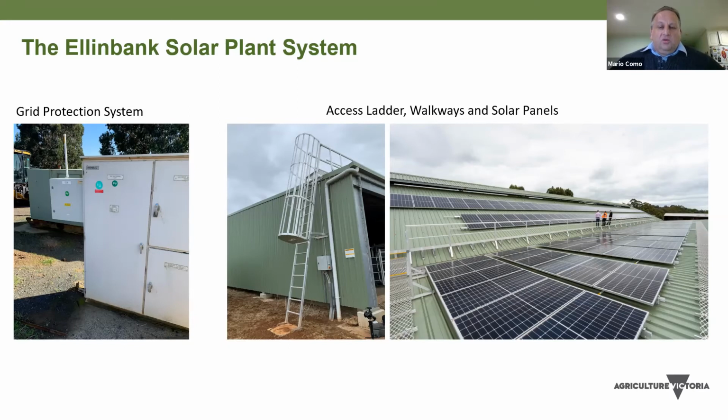We selected not to put the solar panels on a pitch on the other roof, mainly because it would have occupied a much greater area, because we have to allow for shading. Also, within our budget, the cost of actually creating the stands that configure the pitch will also add to the cost. So, with a 12% efficiency reduction, we thought that was a way to go. I think Geoff mentioned 15%, and we're currently monitoring the efficiency of the system. It has peaked at 102 kilowatts when we've had full sunlight irradiance, which is very pleasing to us.